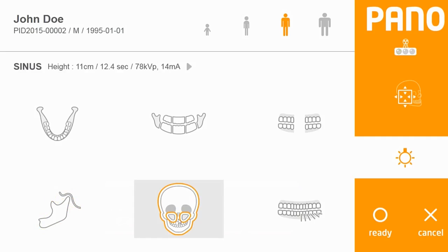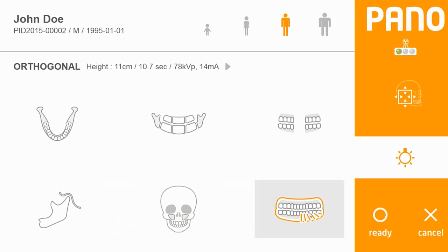The next option gives the two-dimensional sinus. To the right of that is the orthogonal panoramic option. In the orthogonal panoramic, the machine makes a slightly slower rotation around the patient's teeth and does not capture all of the TMJ in the image, but it does reduce some of the overlaps in the image.